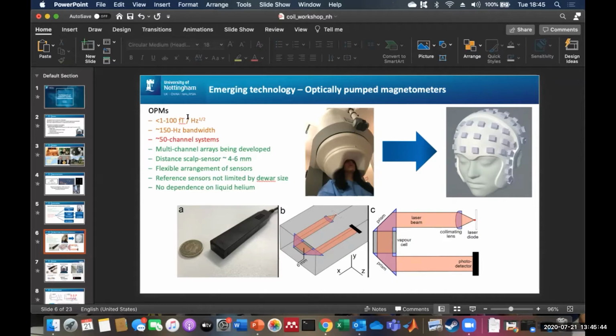The sensitivity of these systems is pretty good. It's about 1 to 100 femtotesla per square root hertz. The magnitude of the activity generated by the brain is around 10 femtotesla to 1,000 femtotesla on the scalp, so that's bang on what we need. There's about a 150 hertz bandwidth, which is also useful for assessing about 90% of the brain activity that we're interested in. Not much goes on in the brain higher than that. We're restricted by the number of channel counts to about 50 sensors, but an advantage we get is that the distance between the scalp and the sensor is reduced from sort of 2 or 4 centimeters to about 5 millimeters.